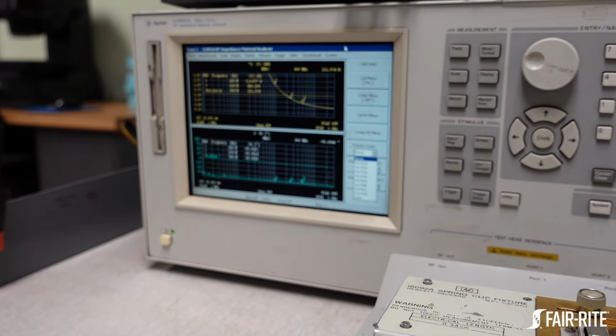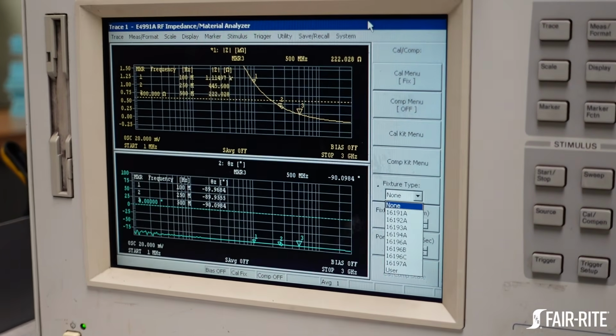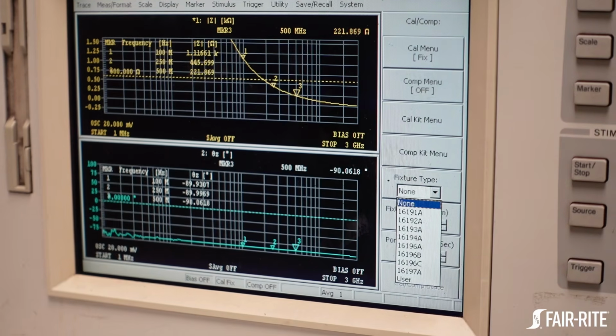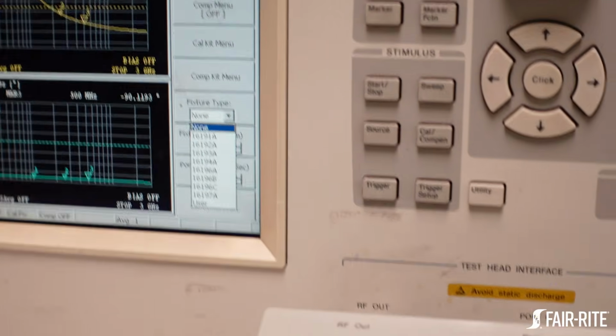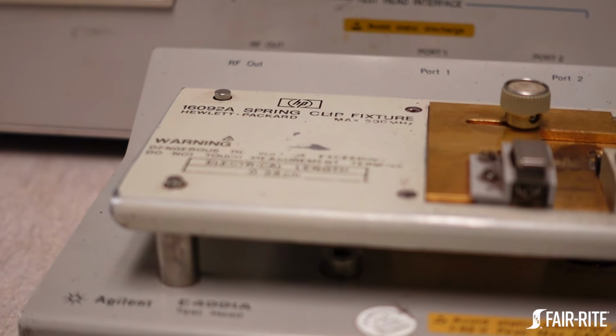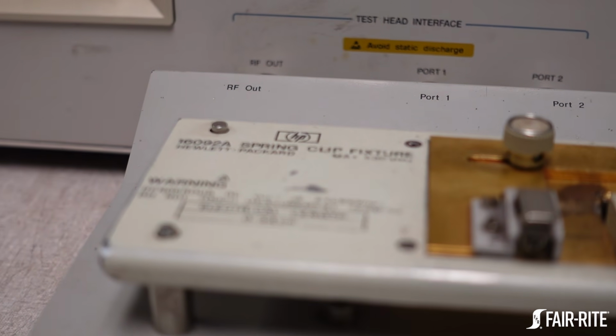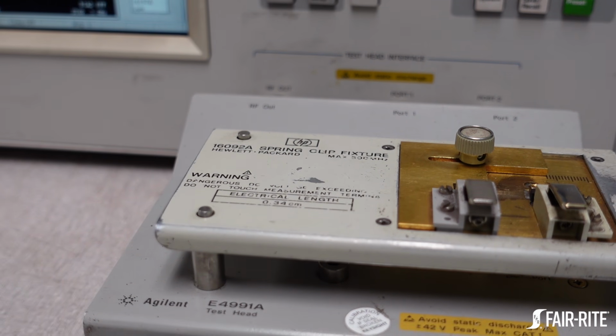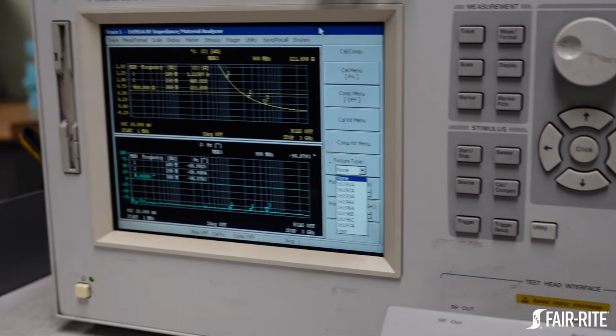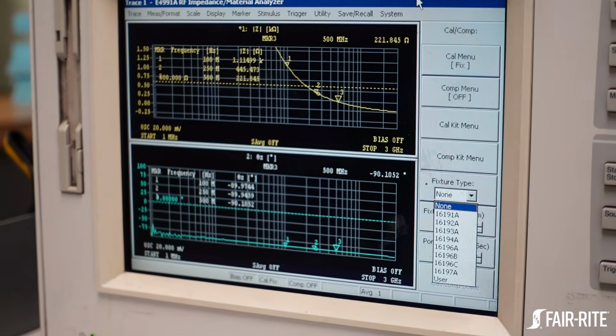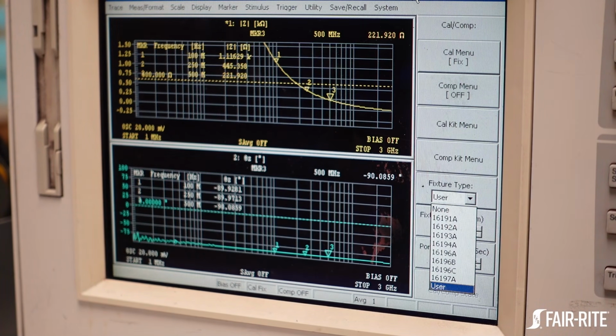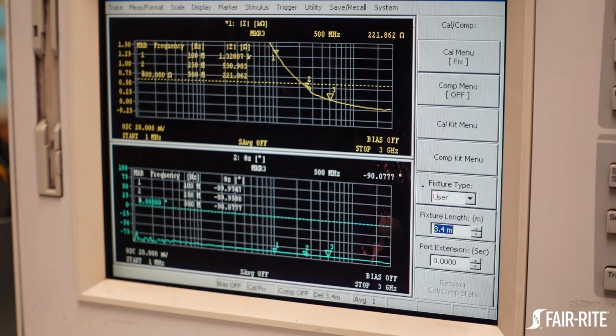Now, this fixture isn't actually one of the selection options inside here, but this fixture has a defined electrical length on it, you might be able to see, of 3.4 millimeters. Now we can actually select a user fixture on here and define a custom electrical length. So we select user, 3.4 millimeters. Now our fixture length is set, and we can go ahead and compensate.